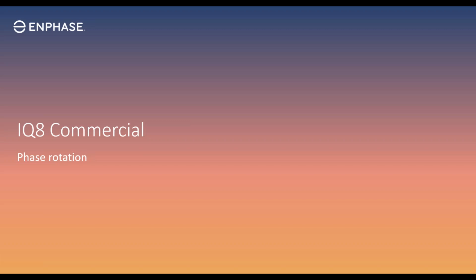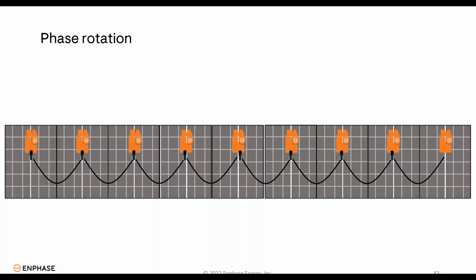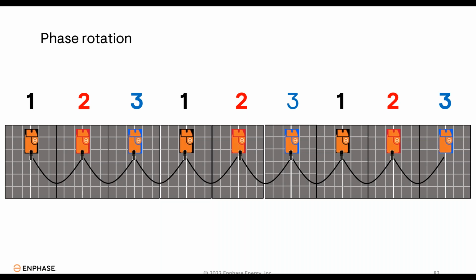Let's talk about how phase rotation works inside the QD cable. This is where all the magic happens when it comes to microinverters putting power on the correct phase. The microinverters produce single phase 208 volt power, and the QD cable alternates that current over three lines—every third connector puts power onto line 1, the next onto line 2, and the next onto line 3.